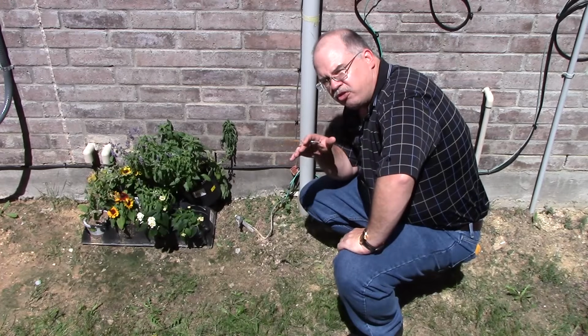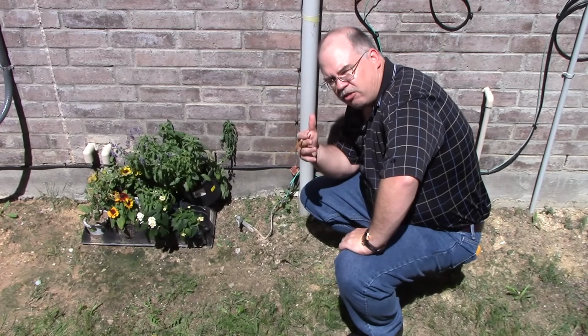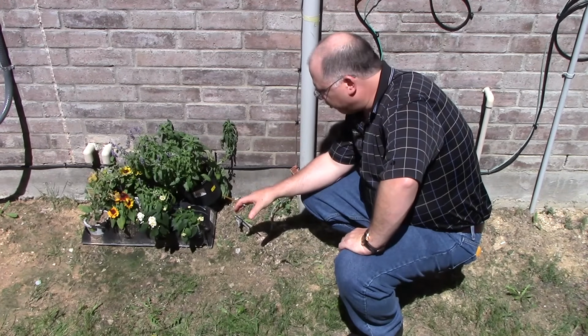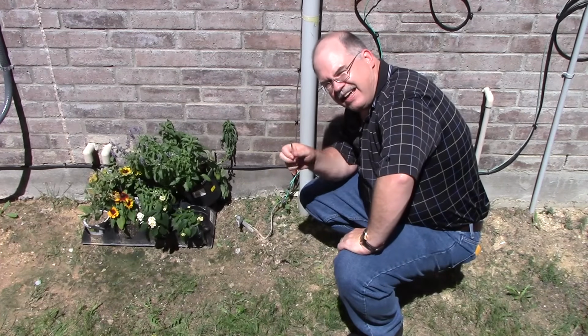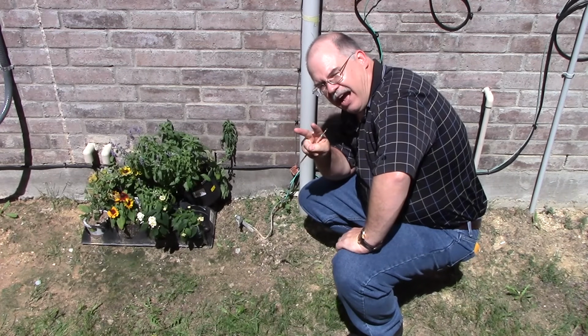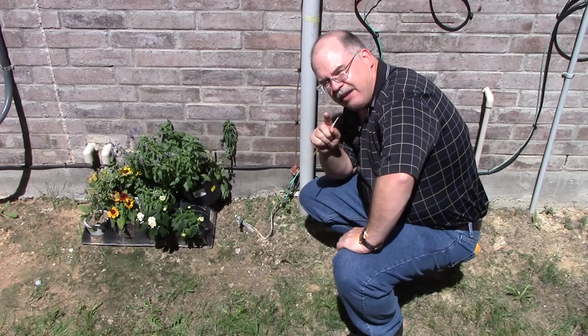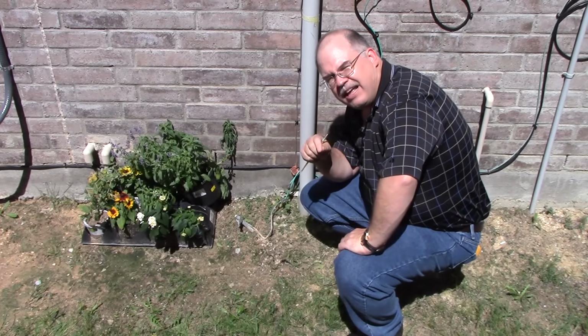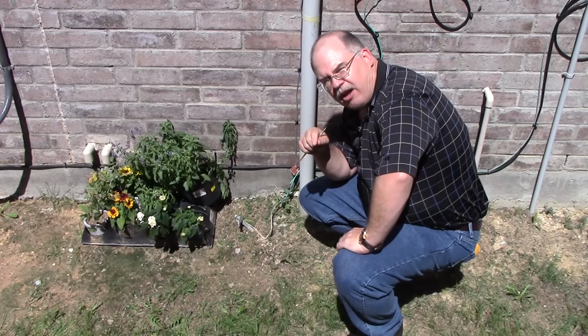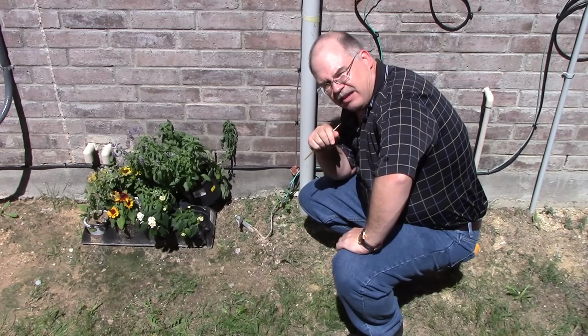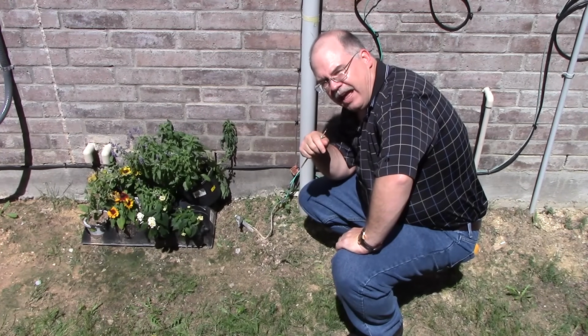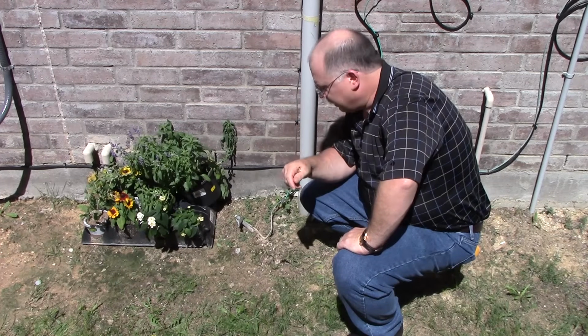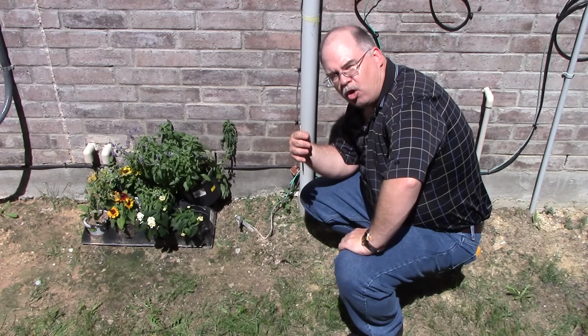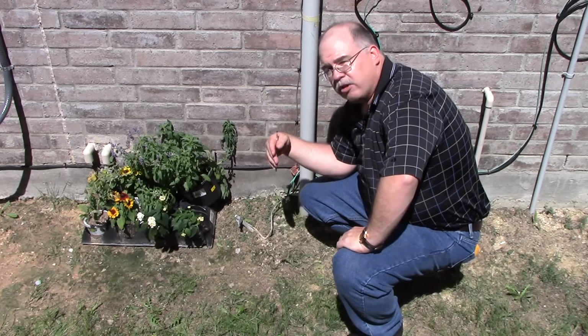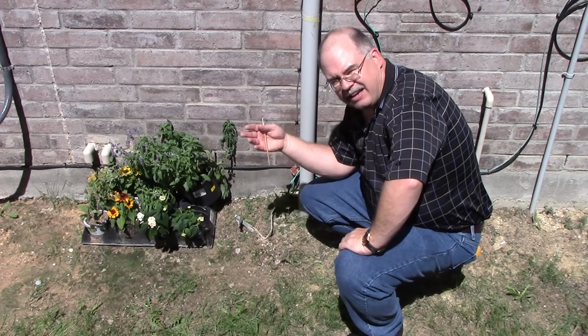Now, if this was your only electrode, the National Electrical Code is going to require that we install, under the 2014, 2 of these ground rods. Now, I can reduce it down to 1 if I can show that that 1 electrode has a resistance to earth ground of 25 ohms or less. Now, if I can't show that, then I've got to install 2. Okay? For a home inspector, you might get an old home that only has 1. So you can recommend as a safety enhancement for them to add a 2nd.